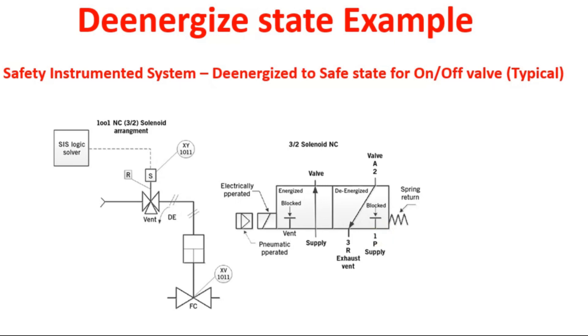Whenever any process condition arises causing a trip or moving the system to the safe state, the solenoid valve gets de-energized and the instrument air connection switches to the exhaust port. That means the pressure inside the actuator body is vented to the atmosphere, the actuator loses its power to hold the valve in the open position, and by means of spring tension the valve goes to the closed position.